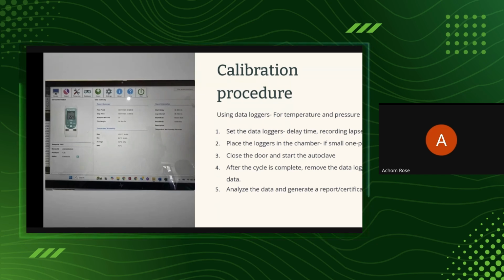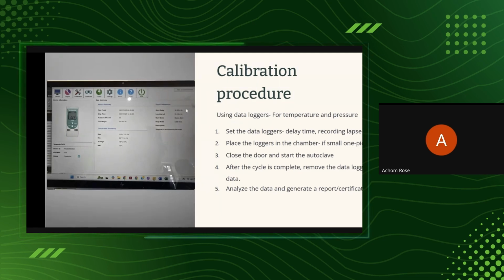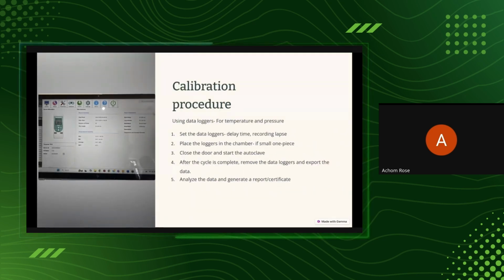After the cycle is complete, you remove the data logger and extract the data. When you extract this data, they normally come as CSV files, which are like Excel files. You're able to read using Excel, analyze this data, and generate a report or certificate. Why we say to analyze the data is that, remember, the logger has started recording maybe immediately or before the sterilization occurred. Remember, our target was to get the sterilization point maybe 121 degrees. So you want to eliminate the readings that were not at 121 before the sterilization started. Okay, so once the sterilization started, that's the time you're looking at. Remember, it is going to record the time for you.